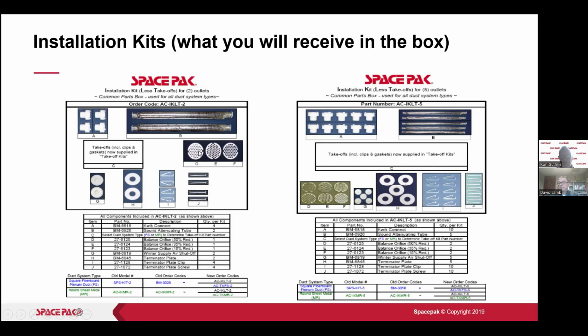The other thing is, if you use one of these, mark the duct with which one you used. Mark the plenum, so if another contractor or another guy from your office comes by, he knows what's in that system. He knows he's not getting much air out of the end of that run because there's a balancing orifice in there. So mark it right on the plenum duct at the plenum takeoff, which is where these go. These come in quantities of 2 and 5, which is conveniently 7.